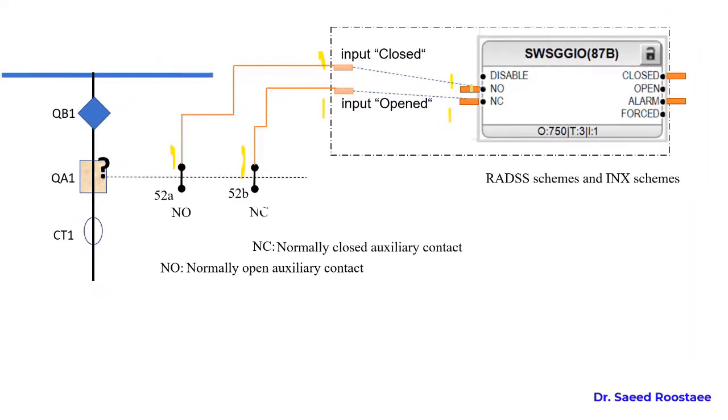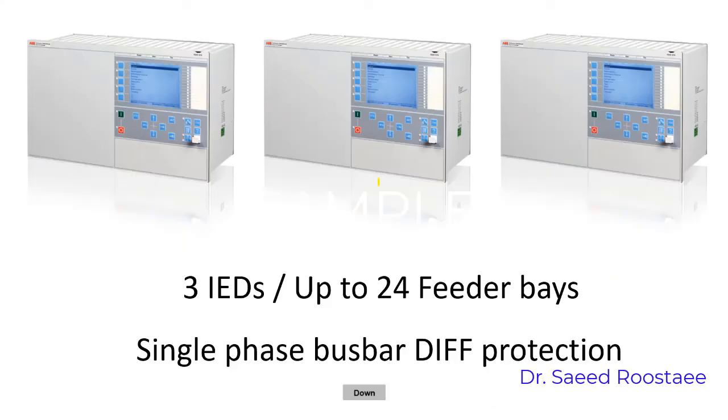In this case the position of the breaker is not clear and for both RADSS and INX scheme it shows the closed position, but with alarm after the T-alarm settings. Also the relay needs more than 24 analog inputs, but the relay limitation can cover only up to 24 analog inputs.